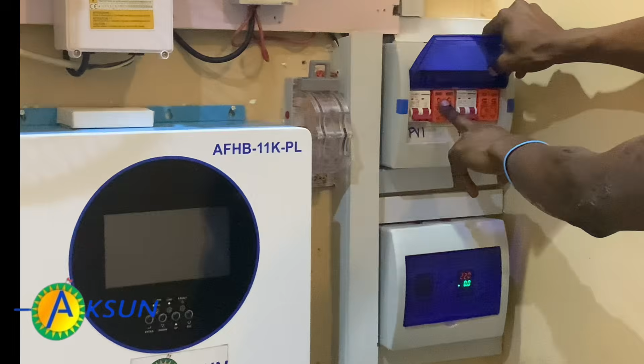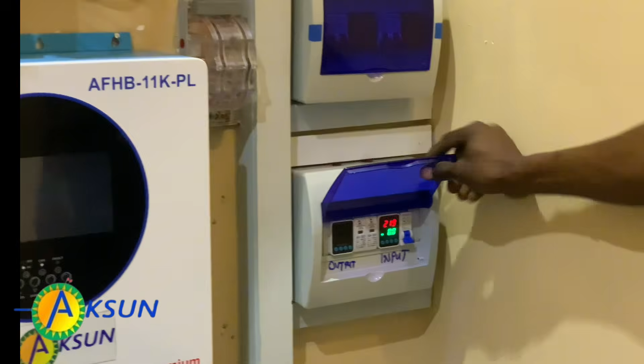We have the breaker for PV1 and the surge, and this is the breaker for PV2 and the surge. That's for the second protection box. We have our voltage protector for the output, and the surge. For the input, I have the input breaker, our inverter, and our double 20 kilowatt CW lithium battery, 20 kilowatts, 48 volts.